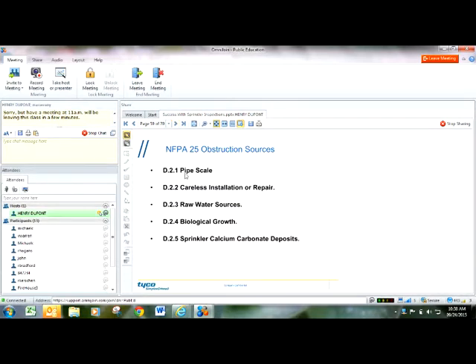These are the most common obstruction sources that we see: pipe scale, careless installation or repair. This, I think, is referring to more of like if you have an underground main break outside of your building and gravel gets pushed into the system. Well, every year you're required to flow water out of your wet systems. Well, that debris and gravel can get washed back into the system.